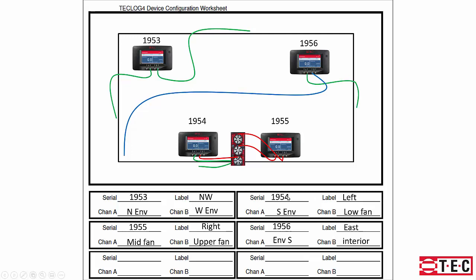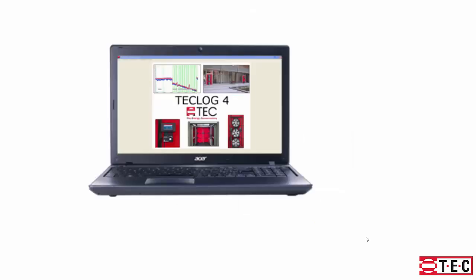Writing down serial numbers and labeling gauges helps identify them — for example, gauge 1953 is labeled northwest corner, channel A going to the north side, channel B to the west. Gauge 1954, called the 'left gauge,' has channel A for south envelope and channel B for the lower fan. Gauge 955, the 'right gauge,' has channel A for middle fan and channel B for upper fan. The 'east' gauge measures south envelope and interior pressure. Then we'll launch the TECLOG software.